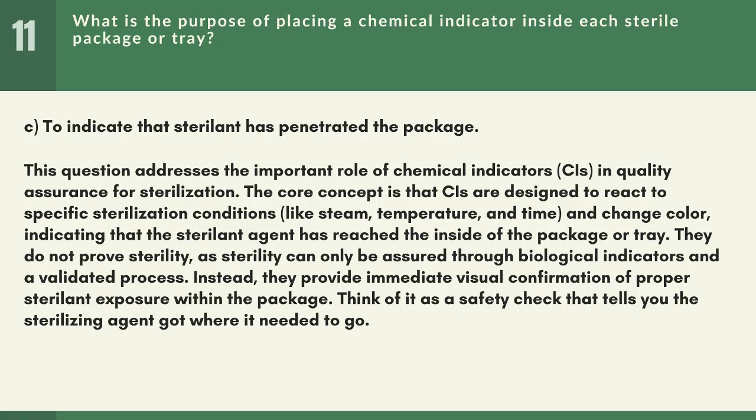They do not prove sterility, as sterility can only be assured through biological indicators and a validated process. Instead, they provide immediate visual confirmation of proper sterilant exposure within the package. Think of it as a safety check that tells you the sterilizing agent got where it needed to go.